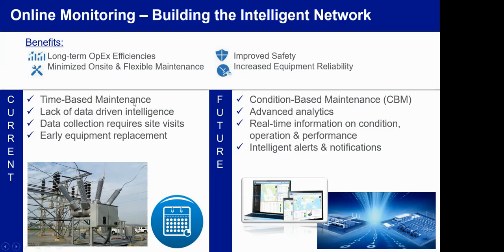Like the manufacturer, the transformer manufacturer, gives that to you and says you got to check X, Y, and Z every 3 years, 4, 5, 10, whatever, under these conditions. So there's a lack of data-driven intelligence, because you don't have any data, you can't really make decisions on the health of that transformer. And if you want to collect some samples, like oil samples, you have to be at the site, because that's the only way you can collect that health data.